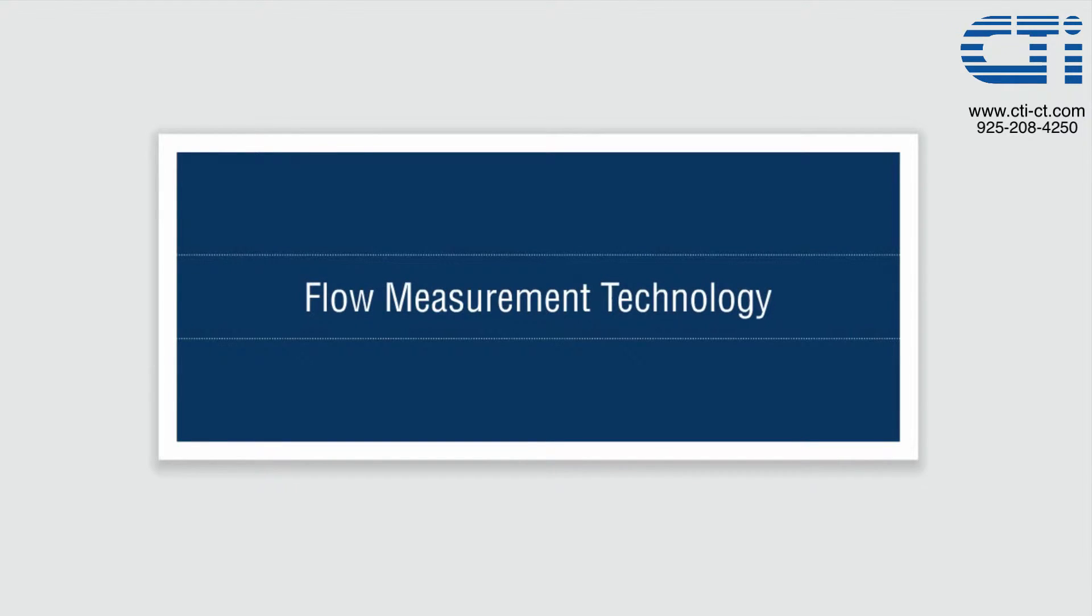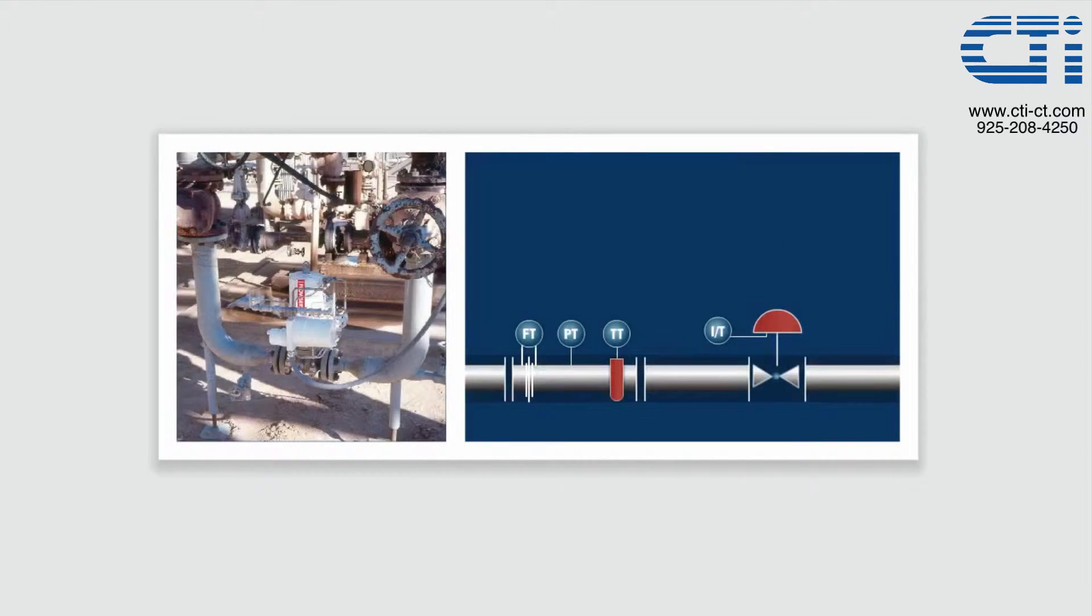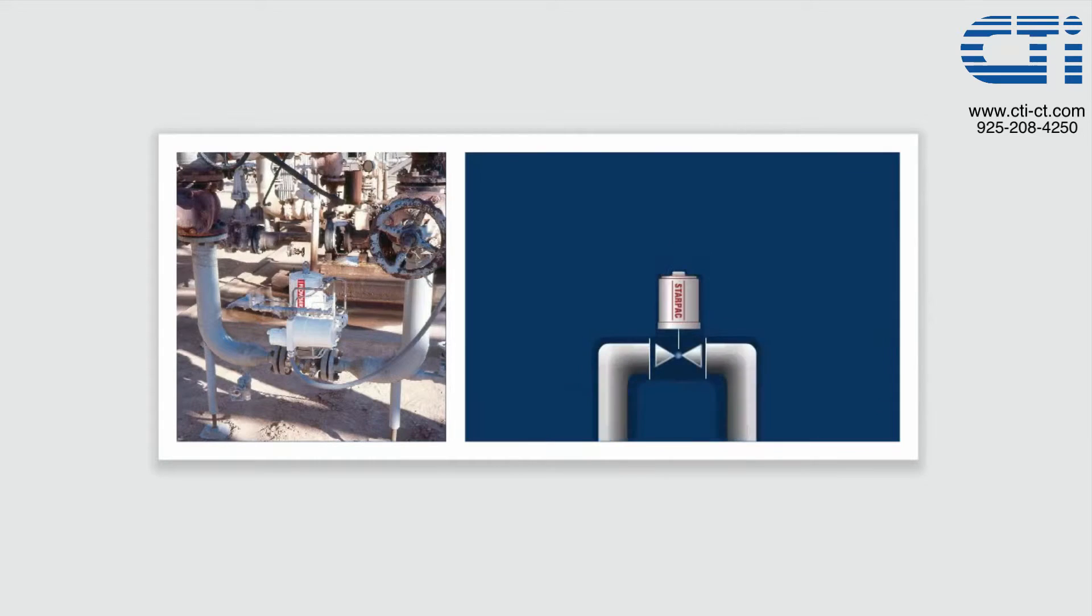Another benefit of the StarPak is the technology it utilizes to calculate a mass flow rate. This is dependent upon the natural turbulence that is created as fluid passes through the valve body, thereby generating its own metering run. This eliminates the need for long straight runs of pipe that traditional loops required to get an accurate flow measurement.